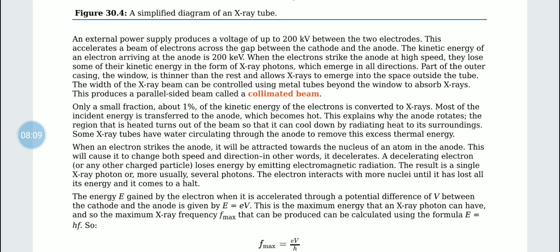That is the reason why it rotates, because when it is rotating, it can provide a newer, cooler surface for these electrons to come and bombard. So that is something that you need to understand. Then also there are cooling systems on the anode to remove these extreme amounts of heat that can get built up on it.